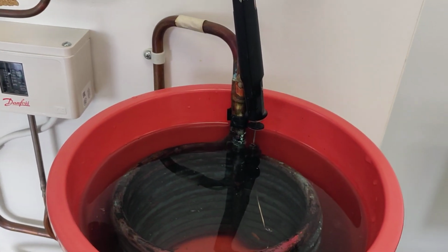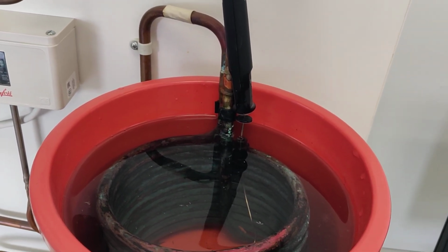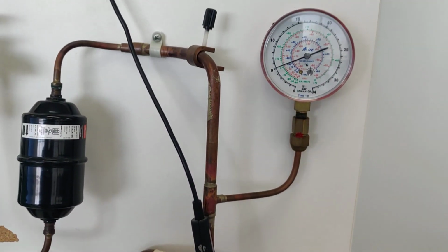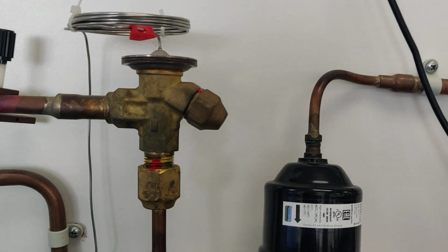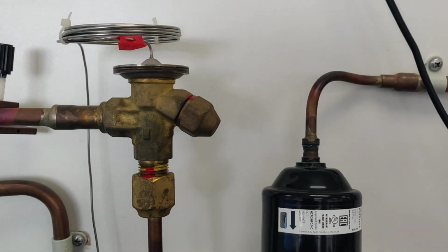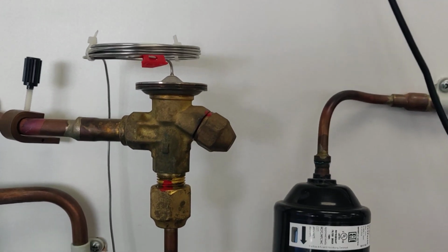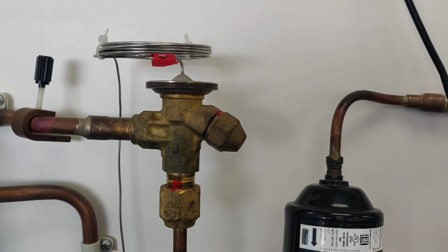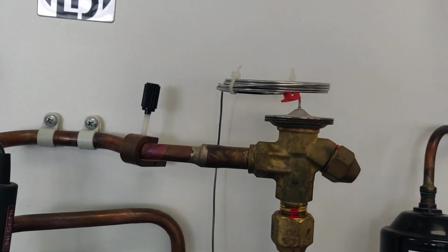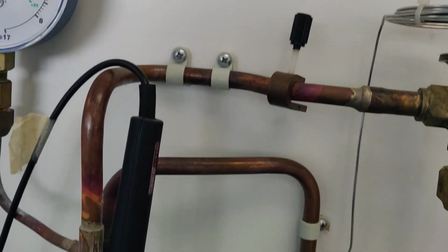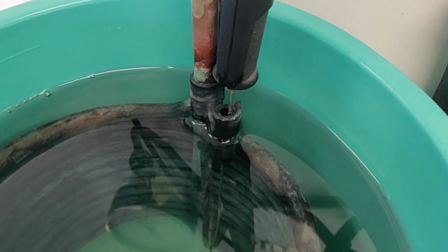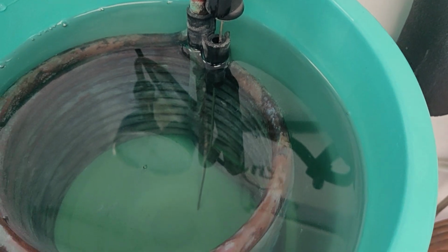Then after losing heat to the surrounding fluid, which is water, the refrigerant travels in this tube further into the expansion valve, where there is a drop in pressure, and due to which there is a drop in temperature as well, and it is very, very cool after coming out of the expansion process here, and it goes in this coil in the evaporator section.